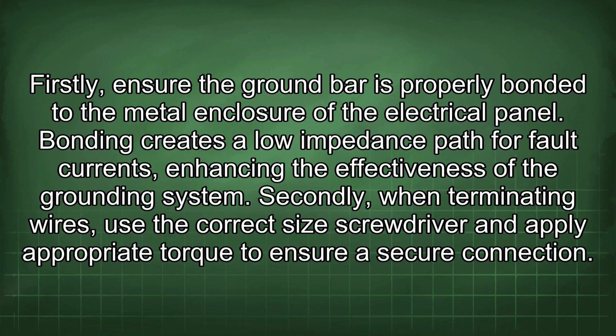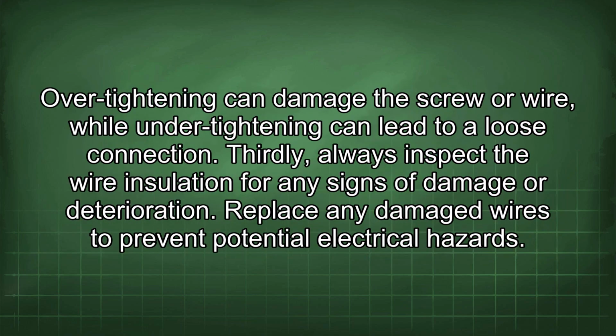Secondly, when terminating wires, use the correct size screwdriver and apply appropriate torque to ensure a secure connection. Over-tightening can damage the screw or wire, while under-tightening can lead to a loose connection. Thirdly, always inspect the wire insulation for any signs of damage or deterioration. Replace any damaged wires to prevent potential electrical hazards.